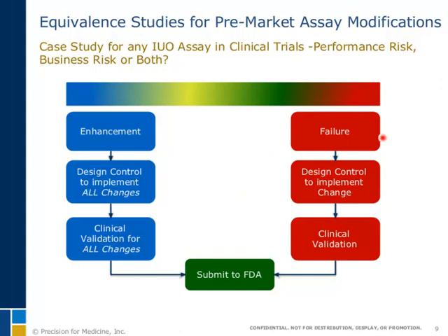From a failure perspective, that's an easy one. If it's a failure, you've got to implement the change, and you have to repeat the validation and submit to the FDA.